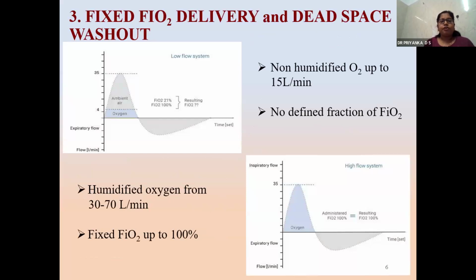And fixed FiO2 and dead space washout, as seen in this picture, which is a pictorial depiction of the low flow oxygen delivery system. The patient is put on 4 to 6 liters of oxygen with 100% FiO2, whereas the patient's inspiratory demand is up to 35 liters. To compensate for that, there is entrainment of atmospheric air with FiO2 of 21%, resulting in dilution of FiO2 and variable FiO2 delivered to the patient, which does not cater to the patient's demand.